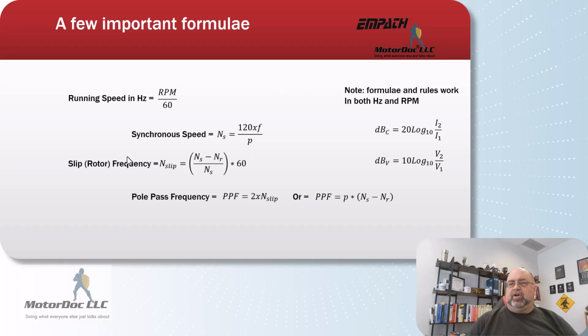A couple of formulas to remember are here. To get hertz, because I like to do mine in hertz, it's RPM divided by 60. Synchronous speed is 120 times the applied frequency. Now this, if you're on an inverter, is the output frequency of the inverter, but across the line, that would be 7,200 at a 60 hertz environment divided by the number of poles. So if a 2-pole motor, it's 3,600, 4 poles, 1,800, and so on. Slip is the synchronous speed minus the running speed divided by the synchronous speed times 60. That gives me that. And in order to figure out my pole pass frequency, if I go twice that, that gives me that pole pass frequency.